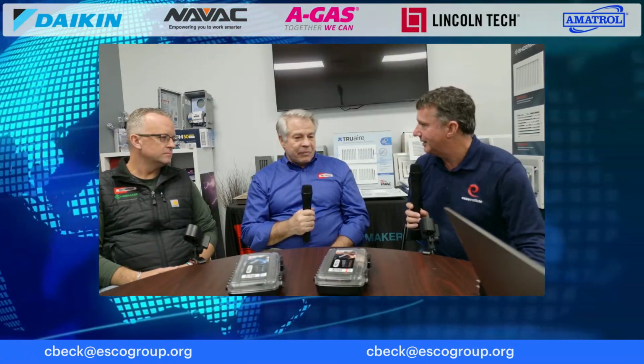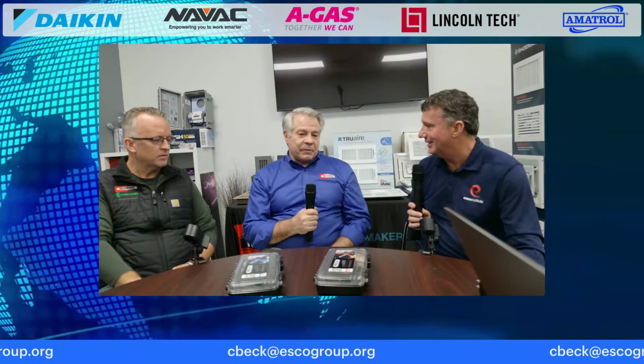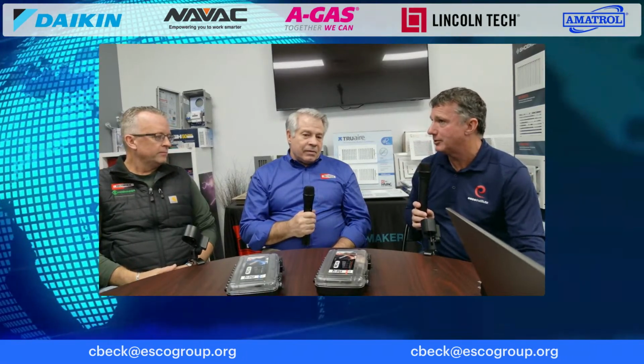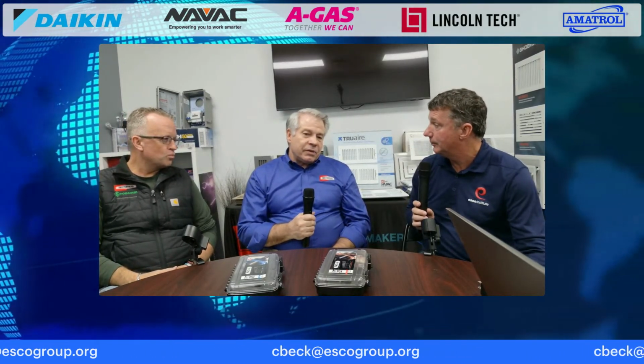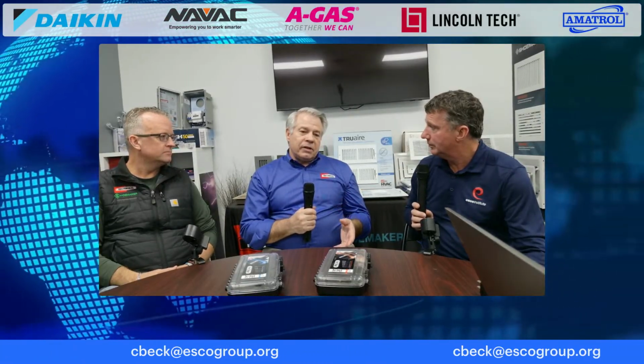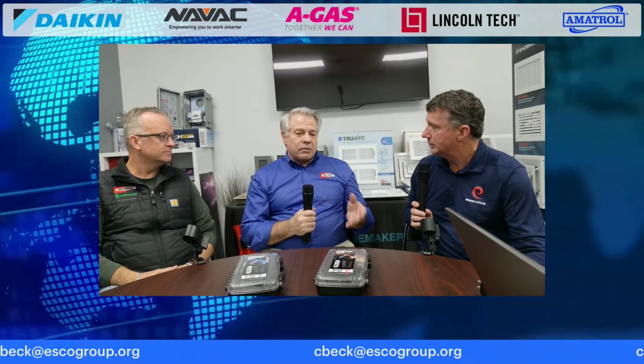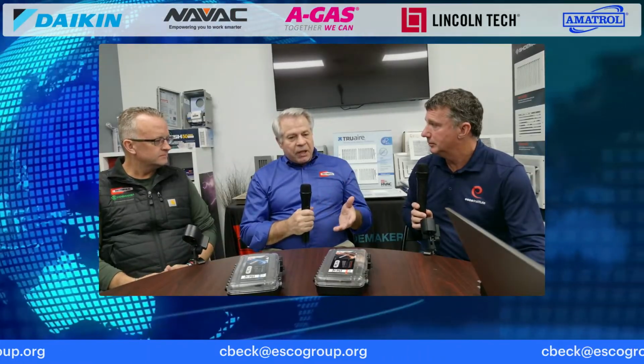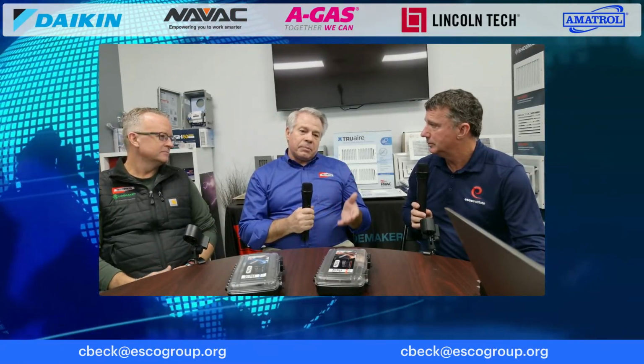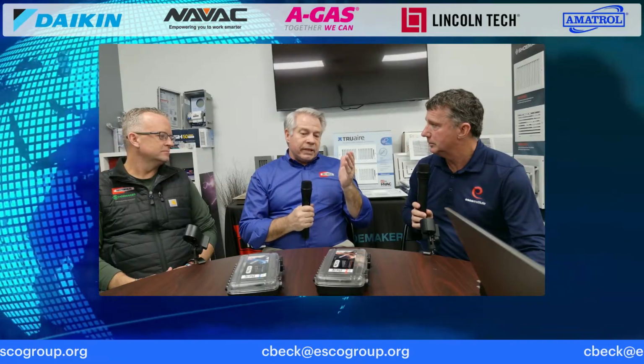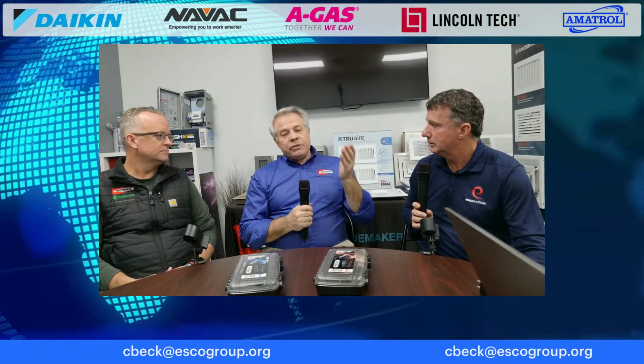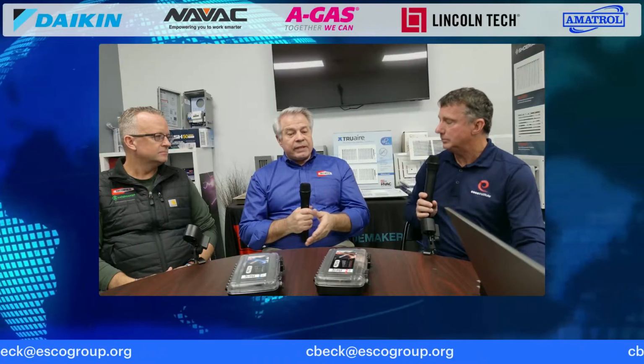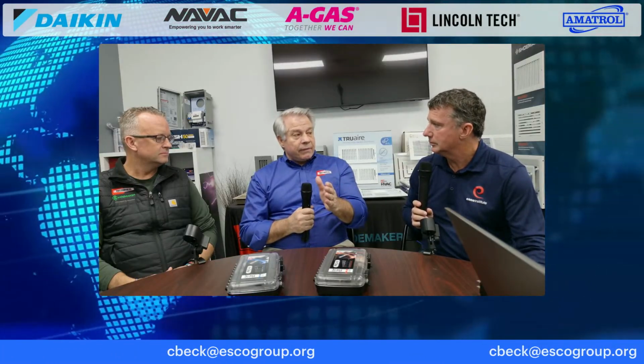Okay. So where do I begin? When I'm thinking about my selection, what factors should I be looking at in my design? When you start your selection, the Air Conditioning Contractors of America, ACCA, have some recommendations in their Manual D. On the supply side, they recommend that supplies are selected between 550 feet per minute to 850 feet per minute, with a design point of 700 feet per minute.